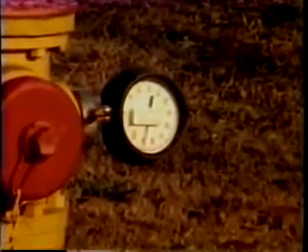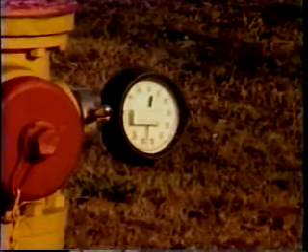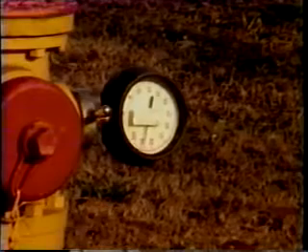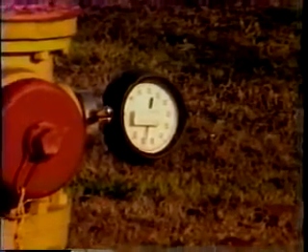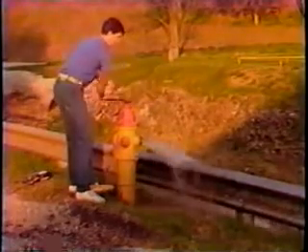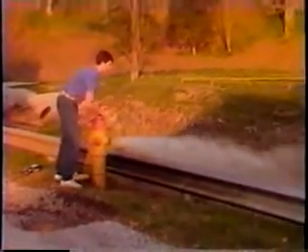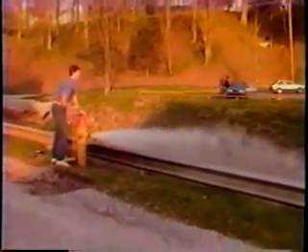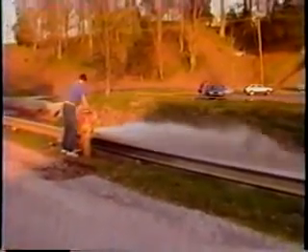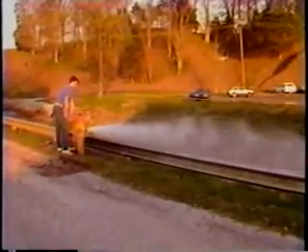Before we talk about what we're going to measure at a hydrant flow test, it's necessary to understand two terms, residual hydrant and flow hydrant. The residual hydrant is the hydrant at which pressures are measured. The second type of hydrant is the flow hydrant. At the flow hydrant, only the discharge from the hydrant is measured. In some cases, there may be more than one hydrant that is flowed, but there's only one residual hydrant at which the pressure is measured.